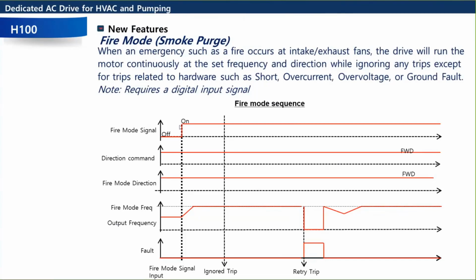So as the fire mode signal goes on, it's going to pick whatever direction. You could have it run forward or reverse, depending if you're running an intake or an exhaust fan, right? You don't want to be pulling in fresh air and adding more fuel to the fire again. So you could pick the direction. Then you're going to pick your fire mode frequency, which is usually 60 hertz. And then this is just saying how we're ignoring trips. If there's any trip, it's going to ignore it, unless it's one of the trips on this list here. So we got 1, 2, 3, 4 different trips that are still considered actual trips.